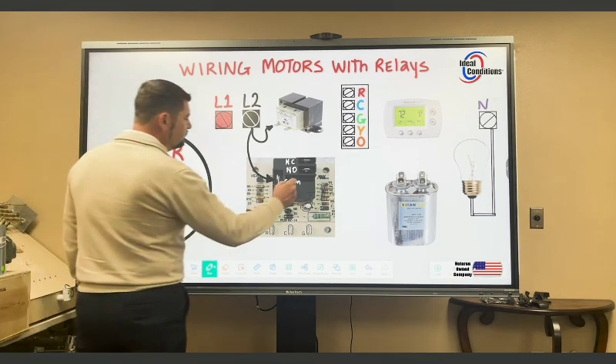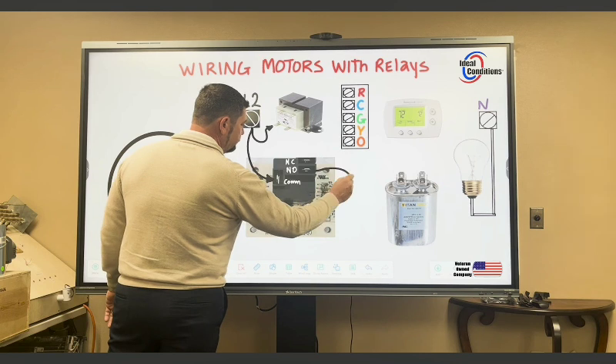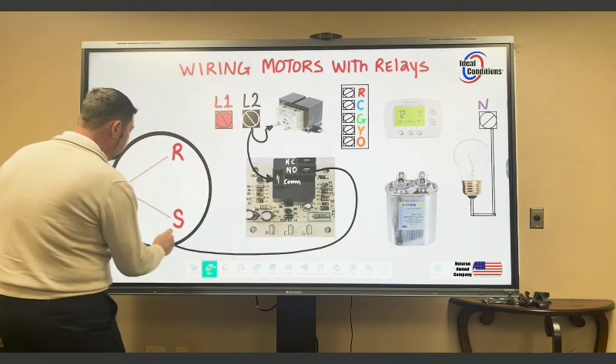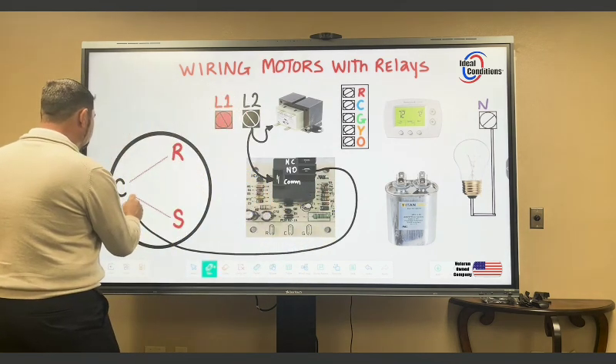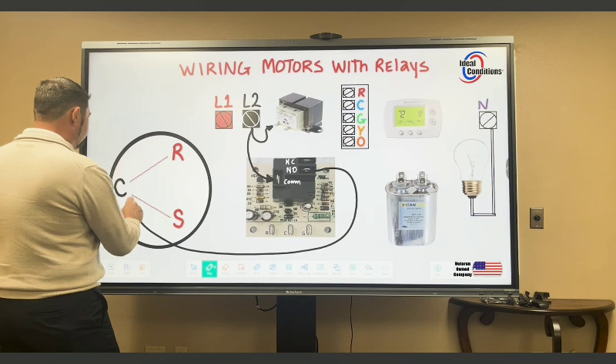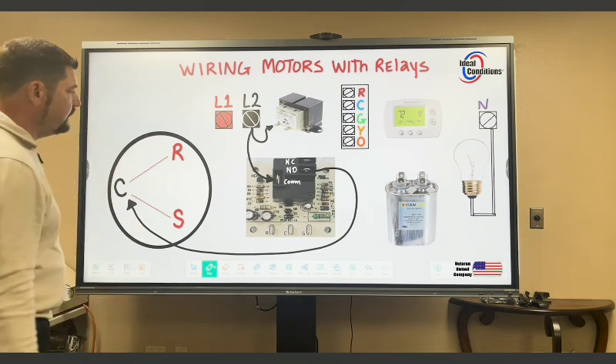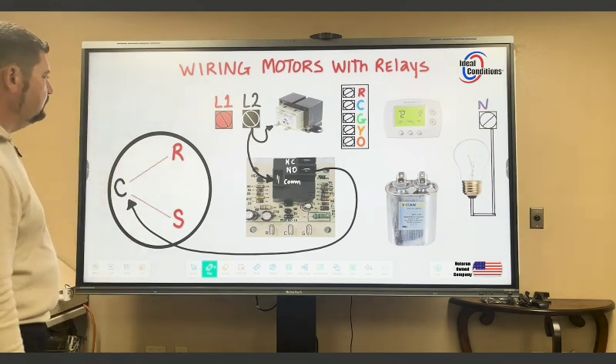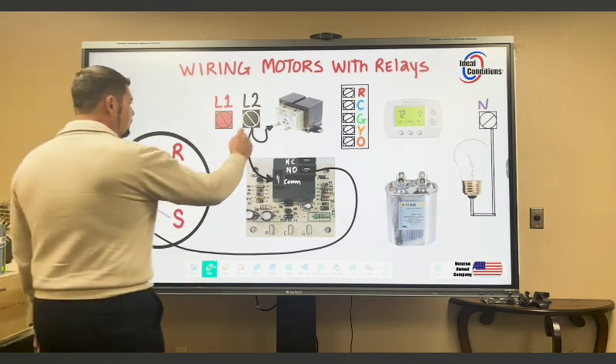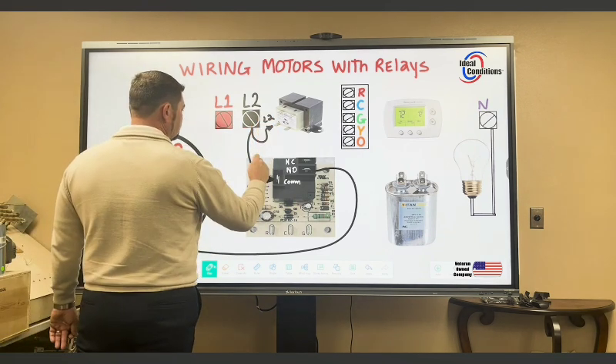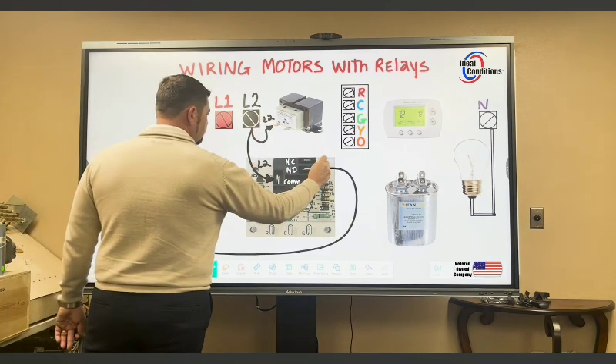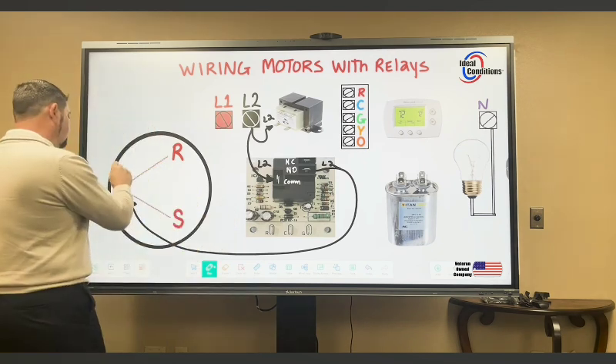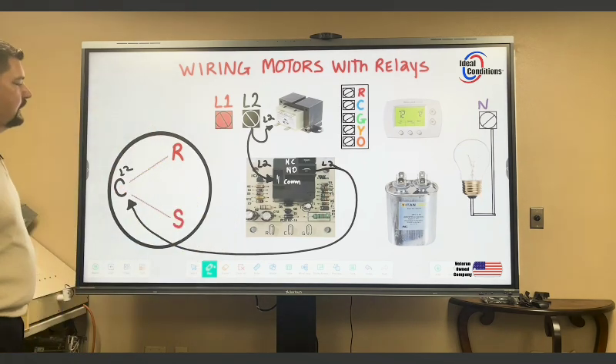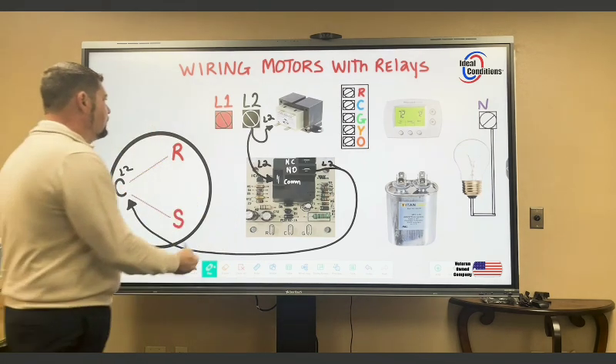And then out of this, you're going to come out of your normally open, and you're going to wire your common terminal. You're going to step back, inspect it, see if anything else needs to happen. You're going to go ahead and just check them off. Everything looks good. All right, I'm going to now go ahead and wire up my L1.